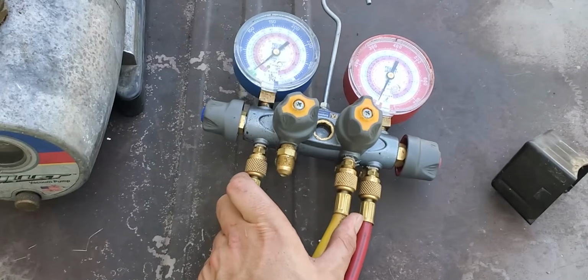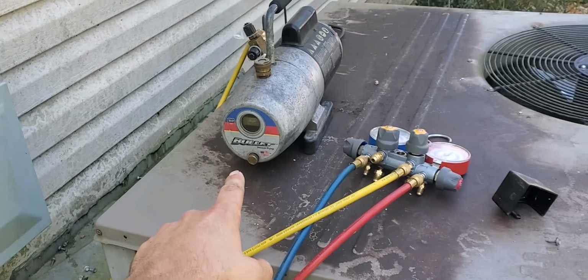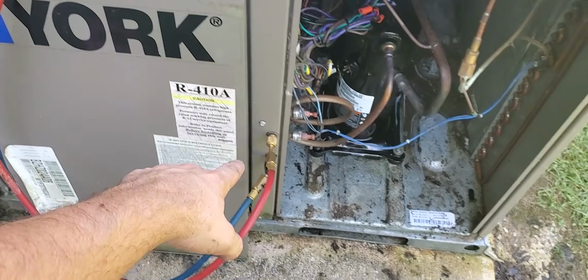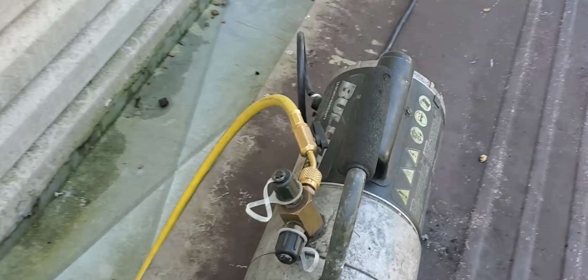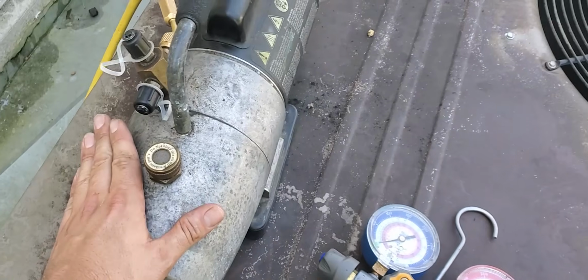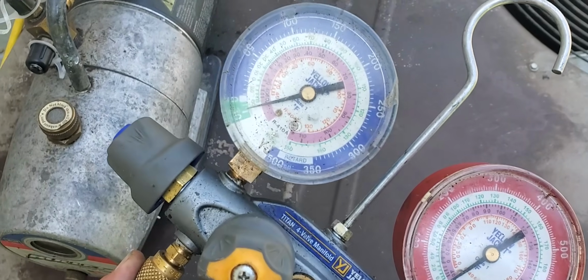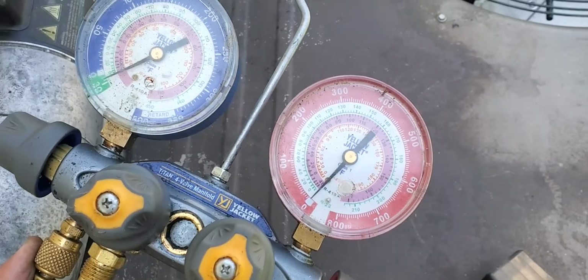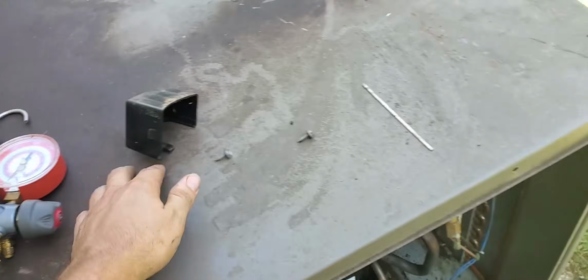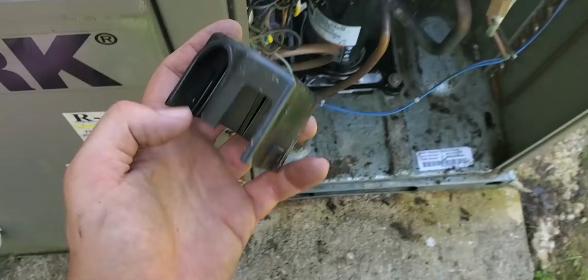So I got the gauges hooked up to the vacuum pump. We got low and high side hooked up to the package unit. And then I've got my pump hooked up and you can hear it sucking. So we're in good shape. Now it's pulling into a vacuum.